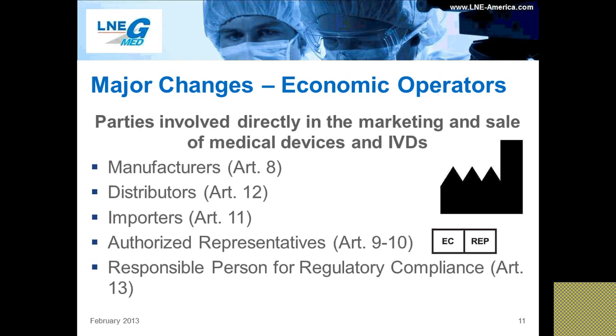A distributor is any natural or legal person in the supply chain, other than the manufacturer or the importer, who makes the device available on the market. Distributors and their obligations are new to the revision, as they weren't included in the directive. However, distributors were mentioned throughout the guidance documents and could have taken over some of the manufacturer's obligations, especially in terms of vigilance. Some of the duties that distributors have include not jeopardizing the IVD while in its care, informing the manufacturer of all the issues that arise with the device while in its care, and of any complaints that it receives.